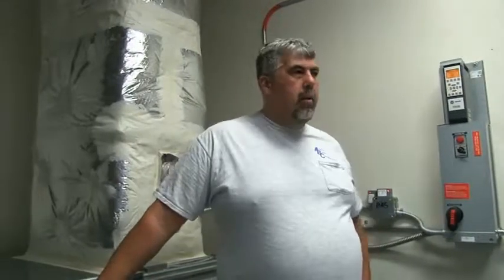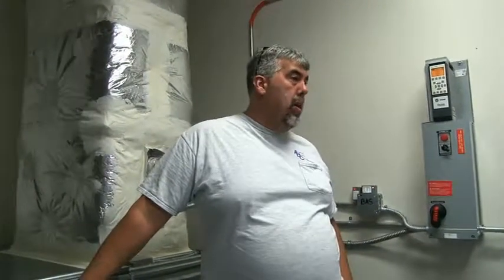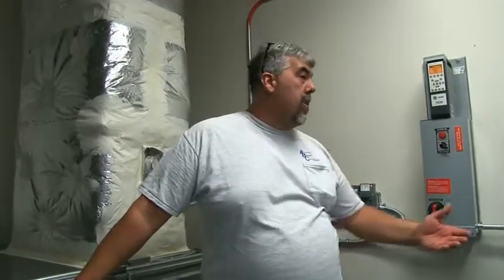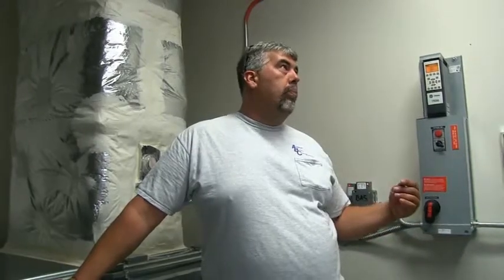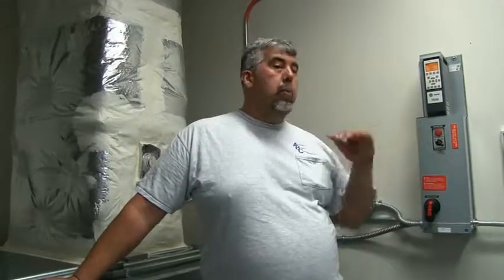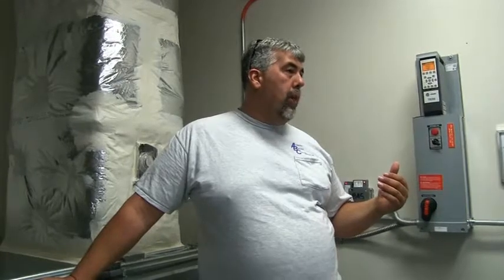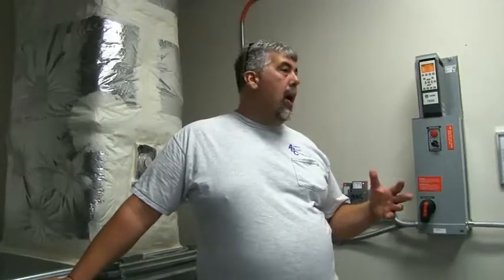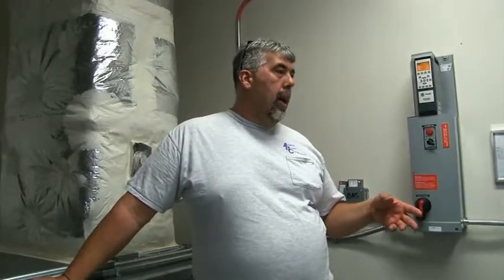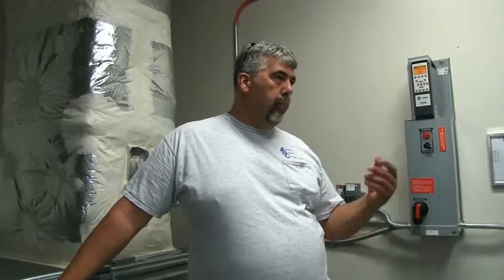I think the reason they don't do that is because the outside air is already probably pretty close to minimum. But the exhaust fans, because you can't pull, for your outside air, you have to bring in 10% more than what you're going to pull out with exhaust. If you do it otherwise, you're going to end up with a negative building, which is a bad thing for you. Every time you open the door, you're bringing in unconditioned air.